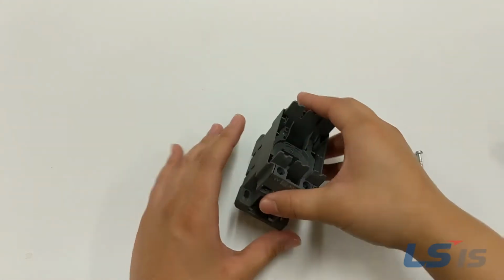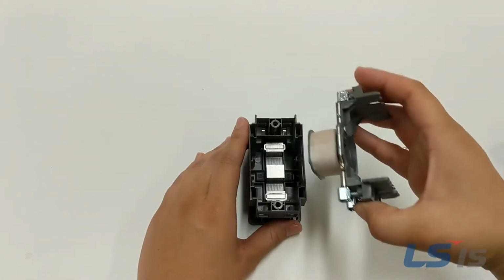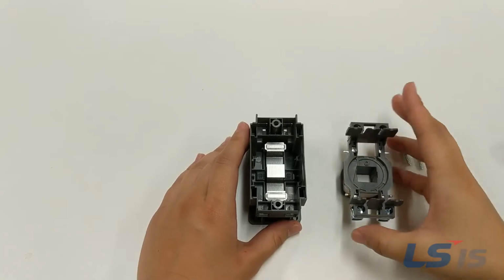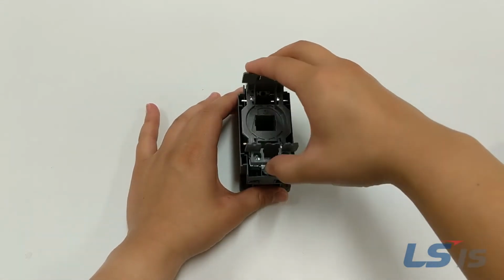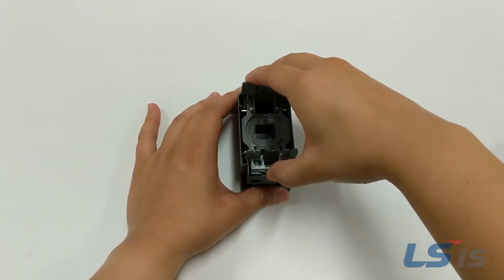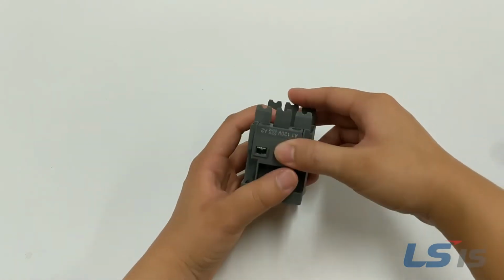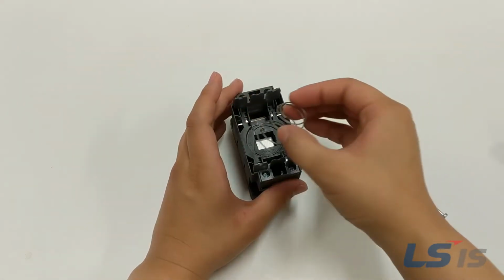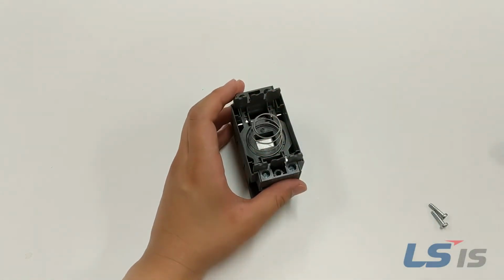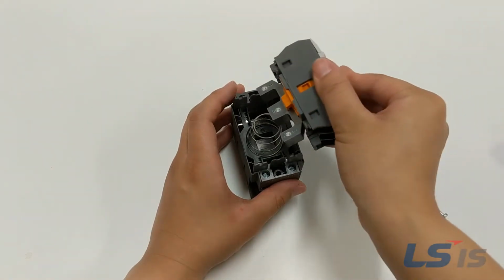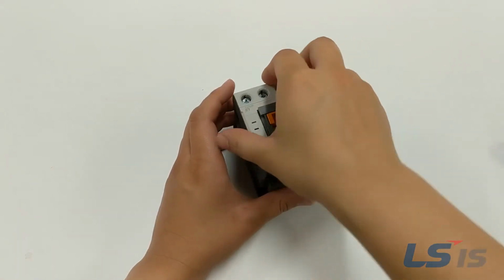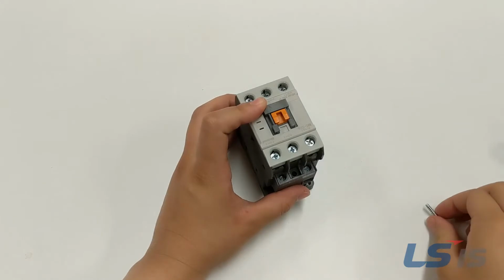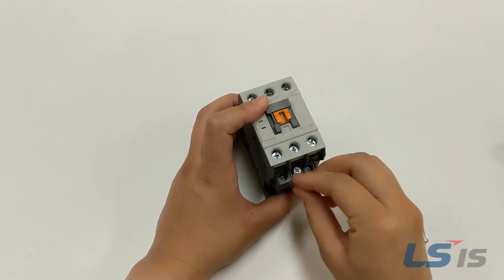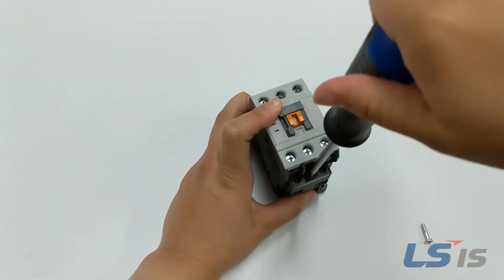Then remove the coil by pulling up on both sets of A1 and A2 terminals. Install the new coil and place the spring back into the contactor with the larger end down. Place the top half onto the bottom half. If the top half does not slide in, rotate the top 180 degrees and try again. Secure the contactor with the screws between A1 and A2 and replace any auxiliaries.